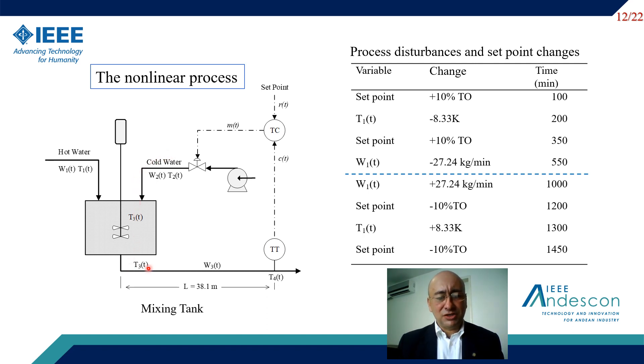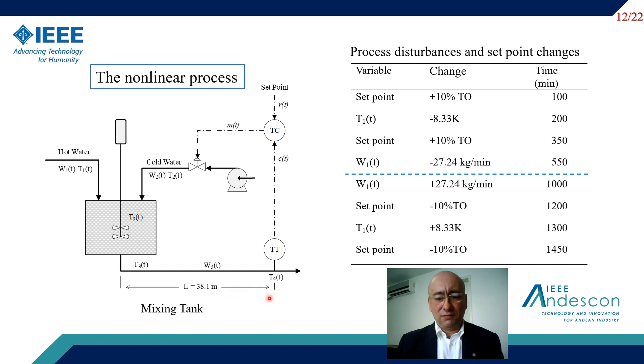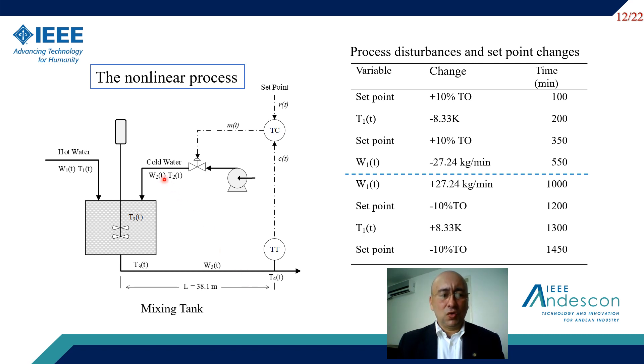The outlet temperature measured at 38.1 meters downstream from the tank is the control variable. This long pipe provides a large and variable process time delay, and the cold water flow is the manipulated variable.